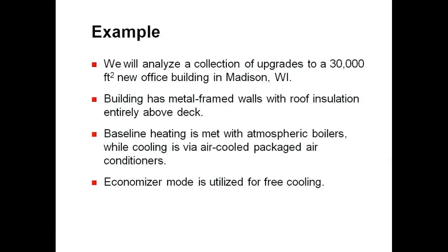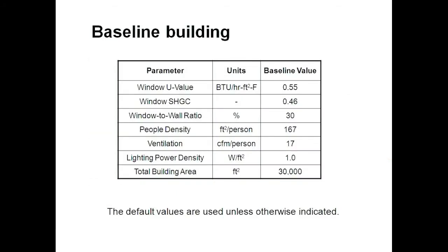For this example, we'll be analyzing a collection of upgrades for a 30,000 square foot new construction office building in Madison, Wisconsin. The building has metal framed walls and roof insulation above deck. Baseline values will be entered for heating via atmospheric boilers and cooling via an air-cooled packaged air conditioner. We will be using the economizer mode. The baseline building parameters are the defaults, unless indicated. So instead of the default values for window U-value, we are entering a code value of 0.55 BTUs per hour per foot squared per degree Fahrenheit.